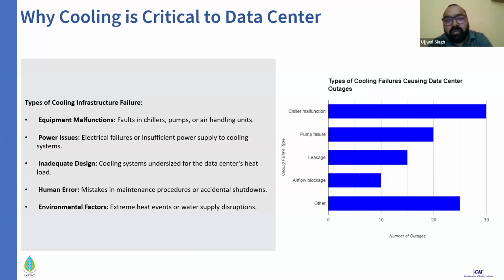If you talk about specifically the failures of the cooling side, then chiller malfunction covers the highest probability out of the total 100%. You can say in 30% of the scenarios where the downtime was caused by cooling infrastructure failure, the real responsible party was the chiller. It could be any fault in the chiller that is causing that failure, followed by pump failure, then leakages and air blockages. There are also multiple other reasons by which the failure can occur, that we will learn in detail in the holistic session that we are going to organize on, sorry, 1st and 2nd July.